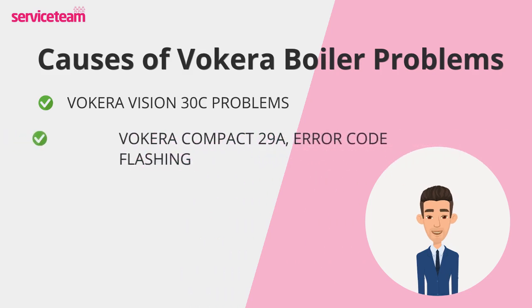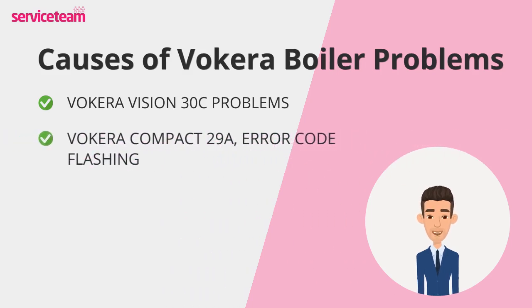The Vokera Compact 29A often throws up error code 03, which usually signals a fan fault. Fans in these boilers are sometimes prone to premature failure due to lower quality components. The most reliable fix? Replace the fan entirely instead of patching it up. Again, professional help is key here for long-term performance.